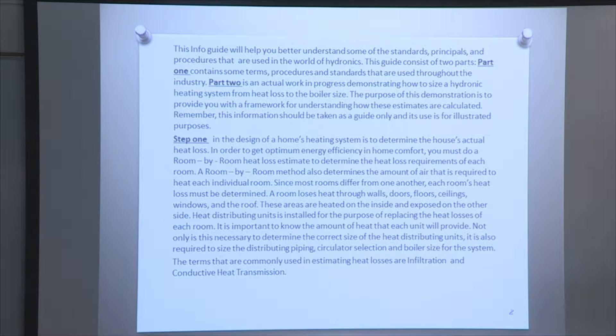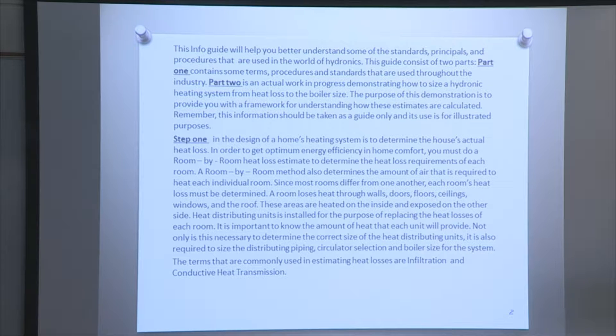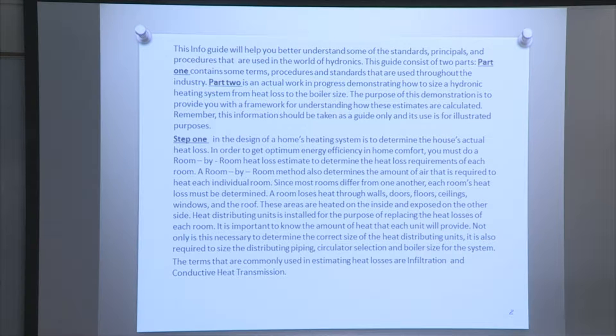Step 1 in the design of a home's heating system is to determine the house's actual heat loss. In order to get optimum energy efficiency and home comfort, you must do a room-by-room heat loss estimate to determine the heat loss requirements of each room. A room-by-room method also determines the amount of air required to heat each individual room. Since most rooms differ from one another, each room's heat loss must be determined. A room loses heat through walls, doors, floors, ceiling, windows, and the roof.